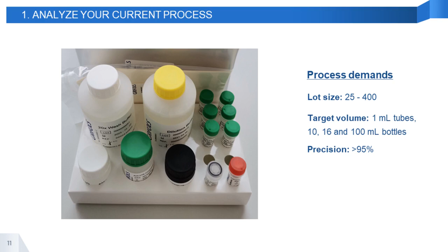And well, which was the solution applied in my company? Changing the filling equipment directly. So I will talk now about the filling equipment that were being used when I started working in Progenika. We have two different ones here. On one side, dispensing pipettes that use tips as a consumable, but in this case, a larger volume can be taken in each tip, and then that volume is distributed in multiple dispensations, so that with one aspiration, multiple dispensations can be done.